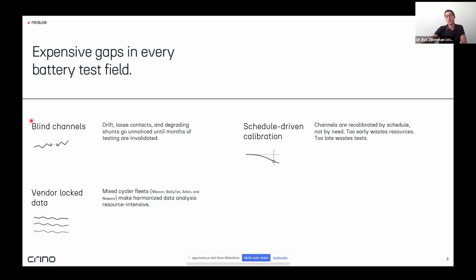Furthermore, there is the schedule-driven calibration, where the cycler channels are calibrated every 12 or 24 months. And the thing is that if you calibrate too early, then you waste a lot of resources and a lot of costs, especially if you also have certification. But if you calibrate too late, you waste a lot of tests, a lot of data. So regarding the quality, we tend to find the sweet spot when each channel really needs the calibration. And last but not least, there is vendor-locked data, especially in battery test fields with a lot of mixed cyclers with mixed hardware. It is quite hard to get out all the data, to harmonize the data, to get a nice export, and also to view it in real time, which makes the assessment and also the algorithmic evaluation of the test quite difficult.